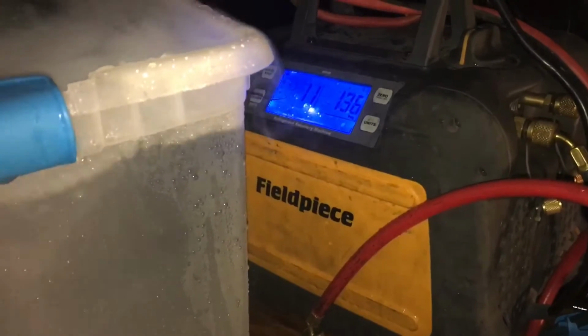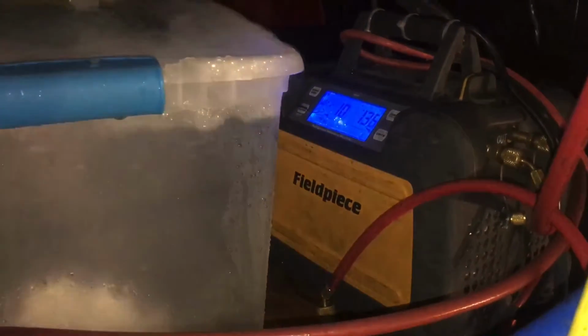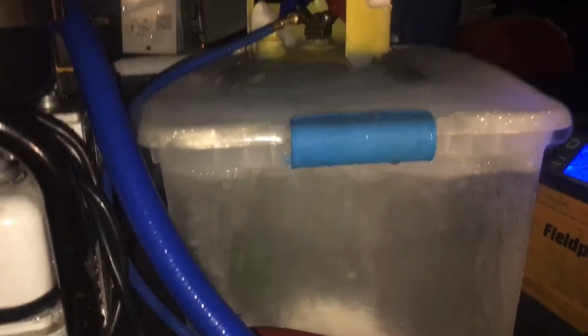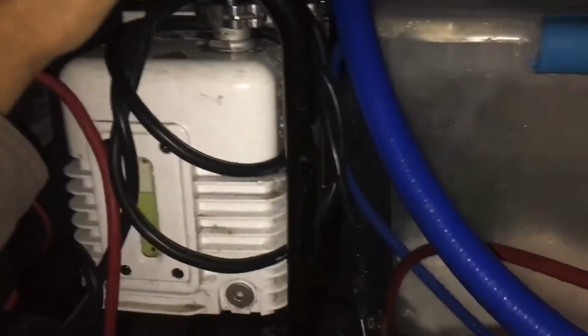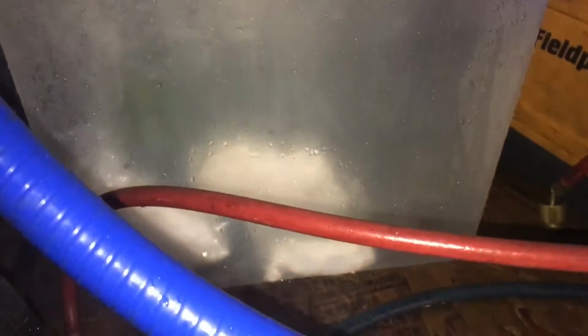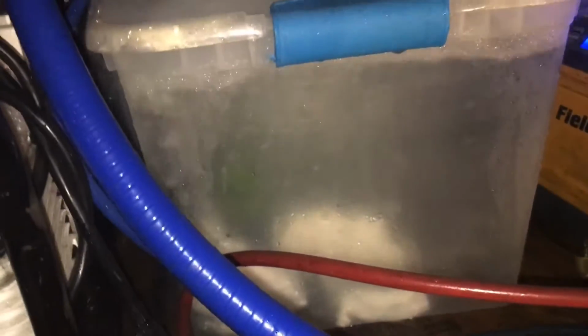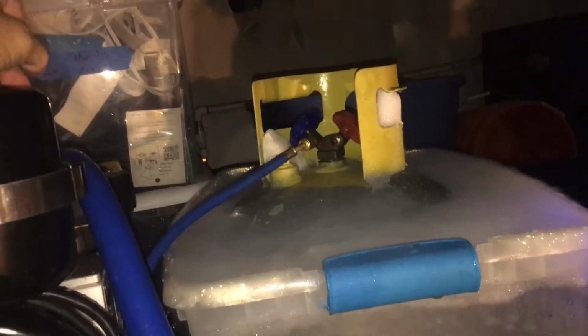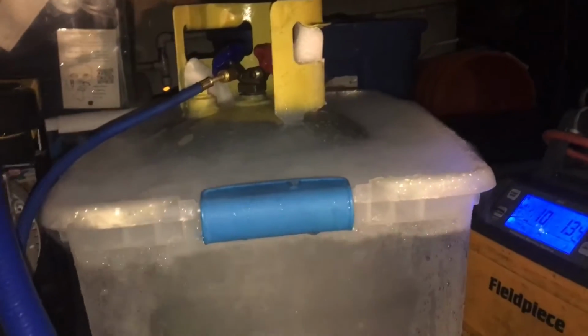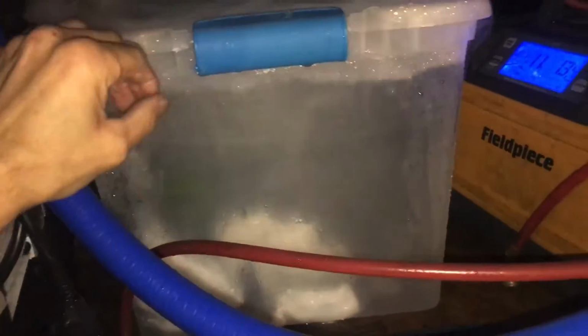We have roughly 5 hours of recovery time so far, and outside has been so cold. We have large accumulators that are located in 2 of the Panasonic HVAC VRF units, and it's freezing up in the accumulator, so it doesn't want to leave. And it's not a hot summer day where all the lines are hot and you have a heavy heat load and you can turn on fans and help move airflow over all the lines and the coils to help move refrigerant.